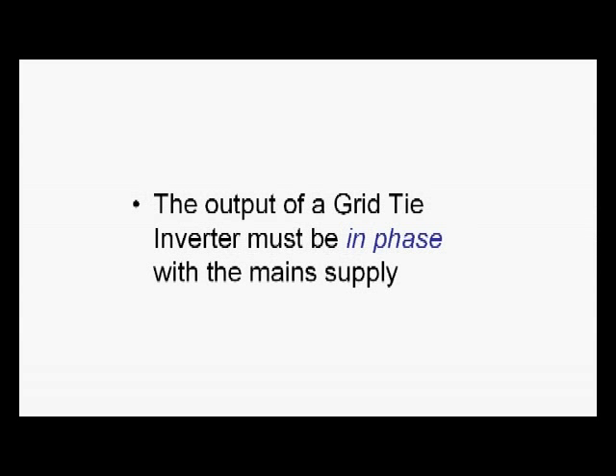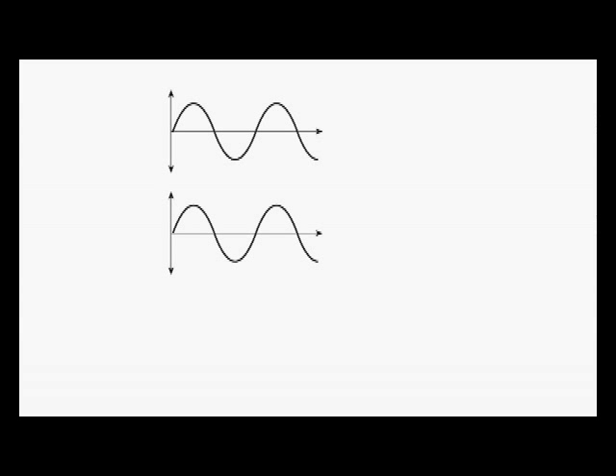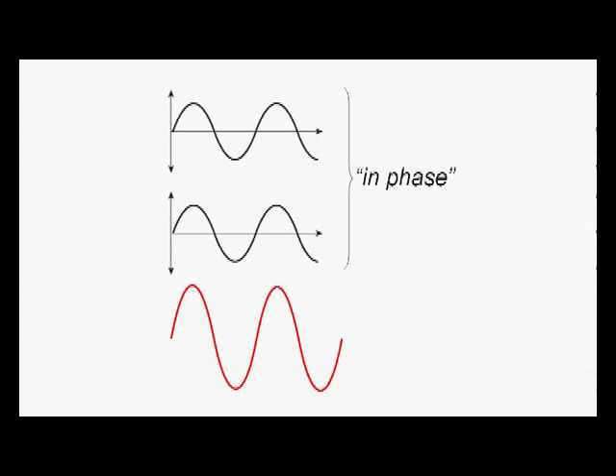Phase matching: the output of a grid tie inverter must be in phase with the main supply. What does 'in phase' mean? If we look at two sine waves here, we can see that they both head up at the same time in their cycle and they head down at about the same time — they're said to be 'in phase.' If those were both electrical supplies and we added them together, the result would be a third sine wave bigger than the first two. We've added one plus one and ended up with two — this is a good thing.